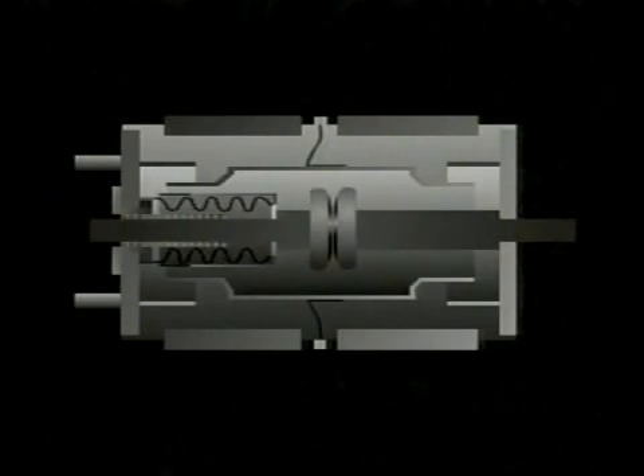A vacuum is an excellent medium for interrupting a flow of current. In vacuum circuit breakers, contacts are drawn apart in a chamber from which air has been removed. When the contacts of a vacuum circuit breaker are closed, current flows through the interrupter. When a trip occurs, the contacts separate very quickly. An arc is drawn between the contact surfaces and is rapidly moved around a slotted electrode surface by a self-induced magnetic effect. This rapid movement limits the amount of electrode erosion and prevents the formation of hot spots on the surface of the electrode.